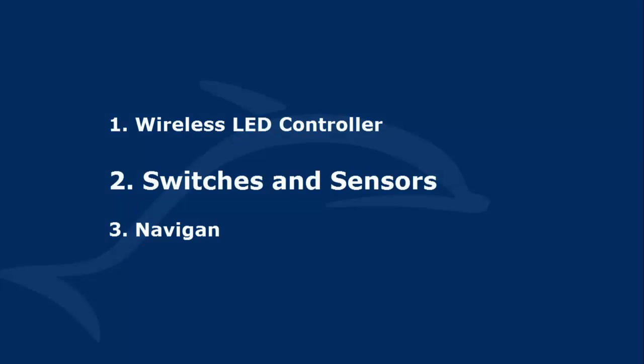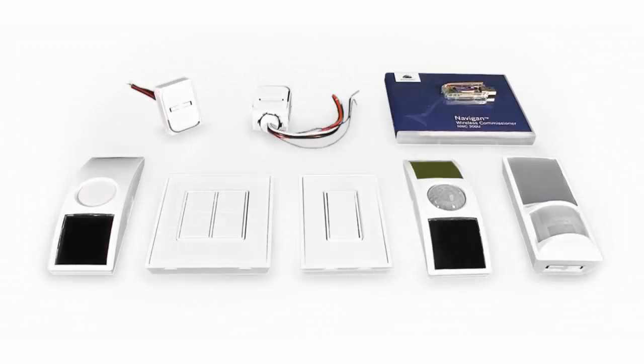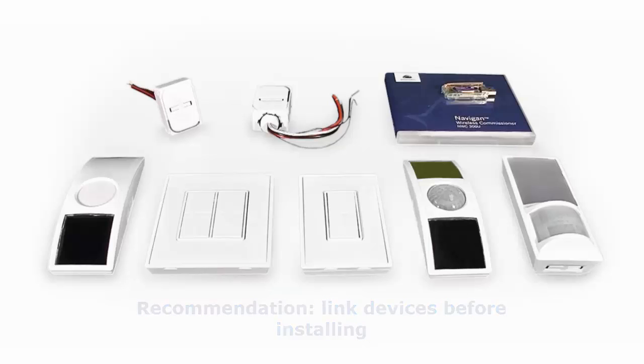Next, switches and sensors. You will want to have your switches and sensors ready, as it is typically easier to link them before installing. Installers can link up to 20 switches, up to 10 occupancy sensors and only one light level sensor per controller.